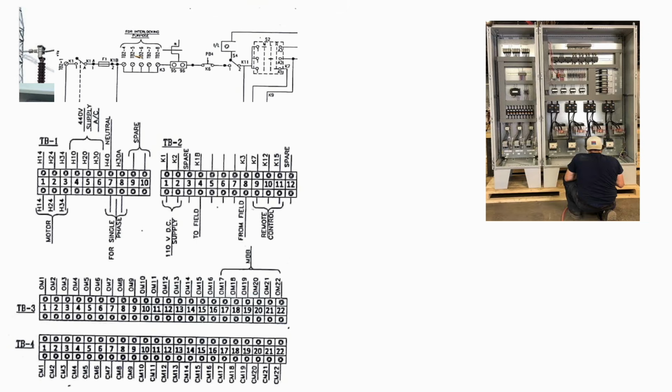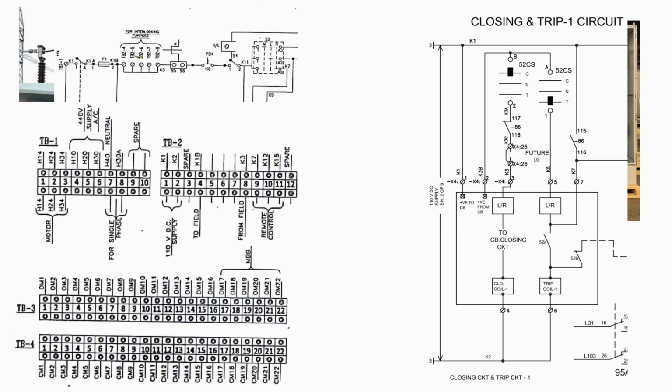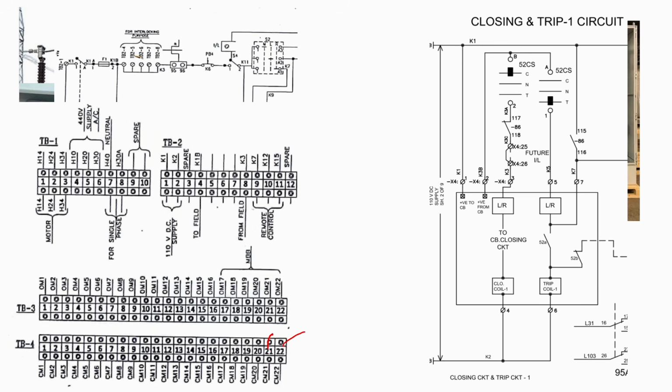Let's discuss panel interlock. We can prevent the closing circuit. We can control the closing circuit from our panel as well. So same phenomena, same philosophy. Okay, here we need to use the 21 22 connection, and you will find this point is the breaker interlock. This is our closing circuit and this is our breaker portion. This is the whole breaker portion, and this side is totally the panel side.